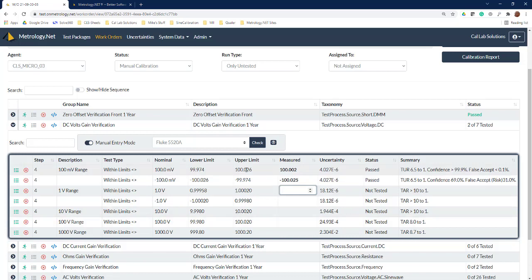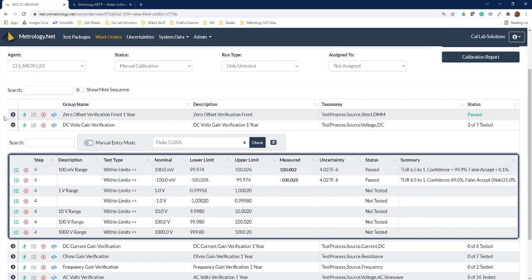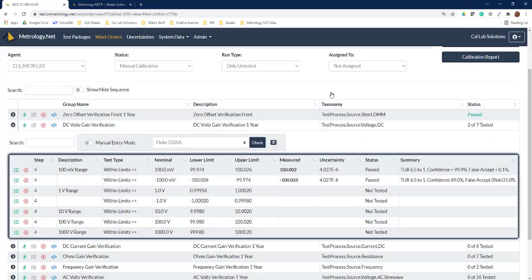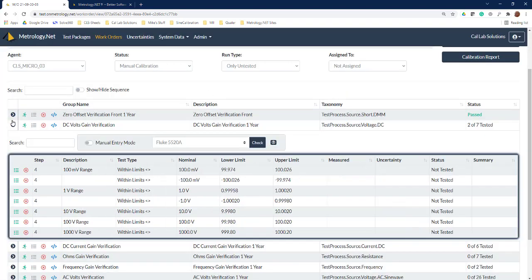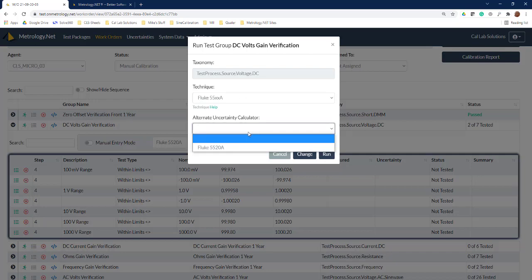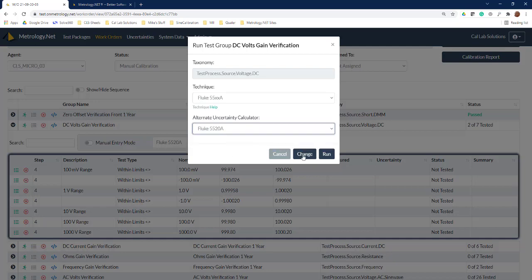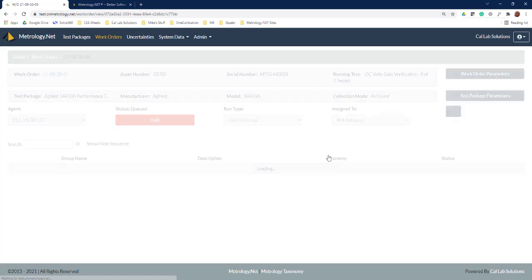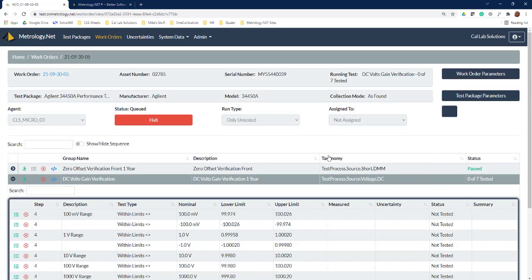Now we want to see how we can run this calibration automated, so we'll kick off the manual entry mode and then we'll reach over here and delete all of our data points. Now we're going to run this automated, so we click run. It comes up with our 5500—we can use the uncertainty calculations that are done inside of the driver or we can pick our customized 5520 measurement uncertainties. We'll go ahead and pick our customized uncertainties and hit run.